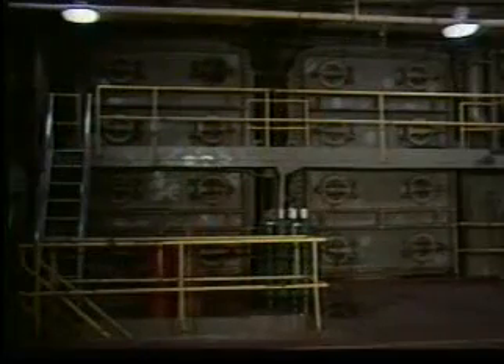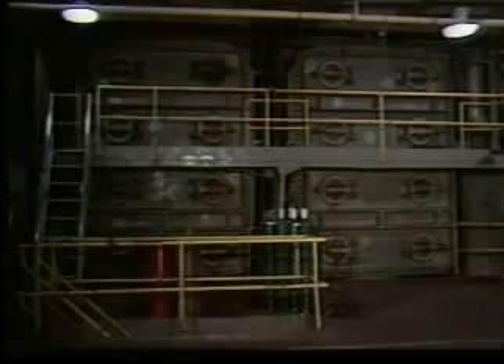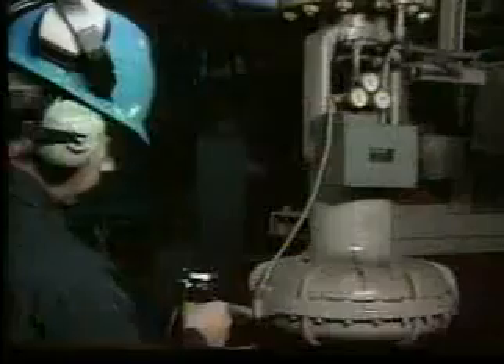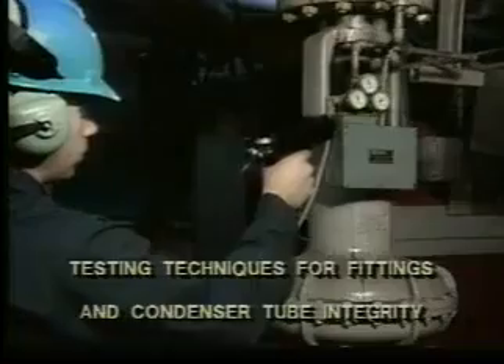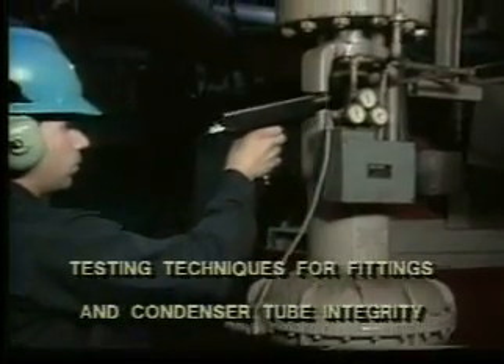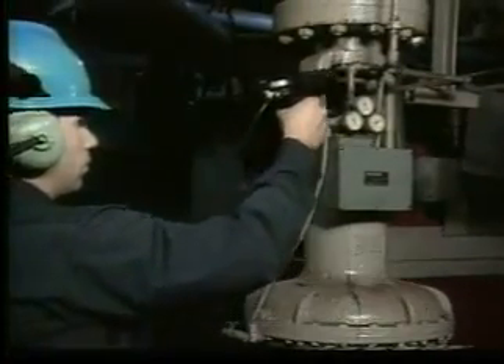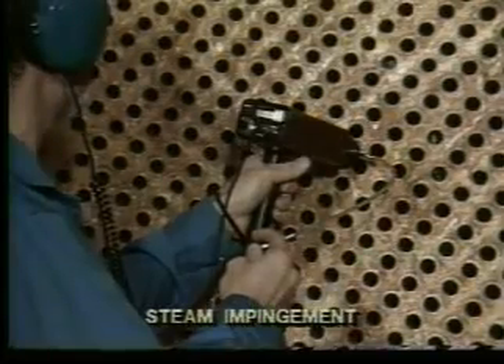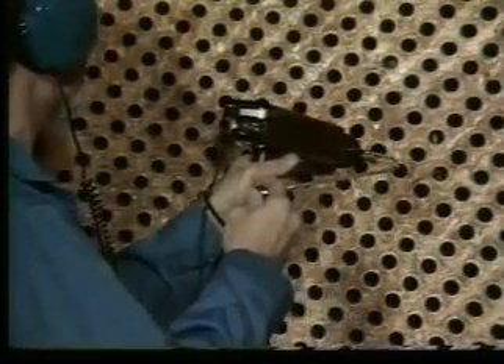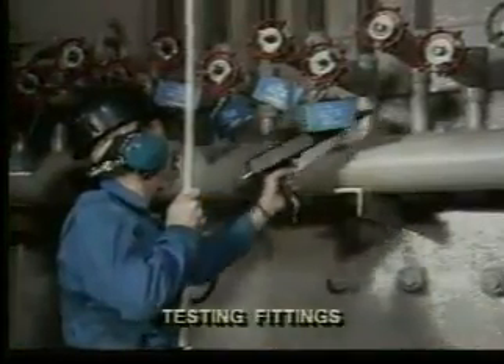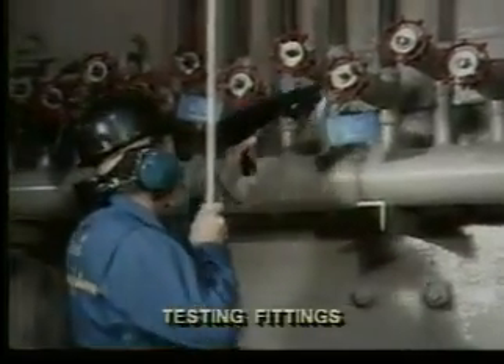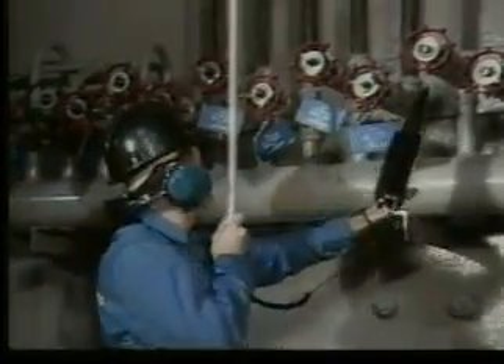Large condensers are usually tested for air in leakage. This introduces impurities into the system and can advance corrosion. We will discuss testing techniques for fittings around the condenser and condenser tube integrity. And we will demonstrate how to handle steam impingement. To test fittings such as valves, piping, and flanges, scan for a rushing sound or white noise.